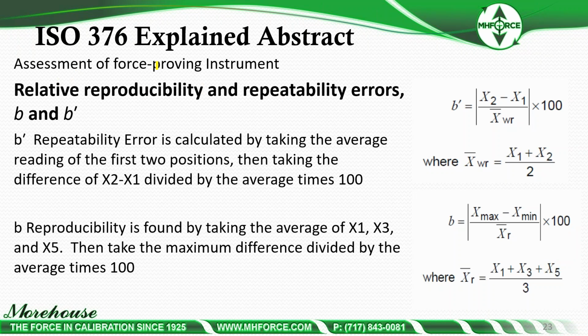So assessment of the force proving instrument, relative reproducibility and repeatability errors, called B. And so how you calculate them: repeatability errors calculated by taking the average reading of the first 2 positions, then taking the difference of x2 minus x1 divided by the average times 100. Reproducibility is found by taking the average of x1, x3, and x5, then take the maximum difference divided by the average times 100. I'm going through this rather quickly, and you can download the PDF and go through it.